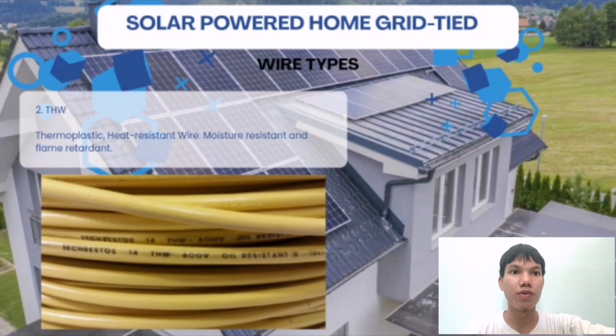Moving forward in our look at critical components, we come to this THW wire. To the untrained eye, it might look like any other cable, but in the world of electrical engineering and solar installation, those letters are a badge of durability. THW stands for thermoplastic, heat resistant, and moisture resistant, where it shares the moisture resistance and flame retardant qualities of the TW we just discussed. The H in THW signifies a significantly higher tolerance for heat. Specifically, the wire is rated for 167 degrees Fahrenheit without the insulation degrading or becoming soft.